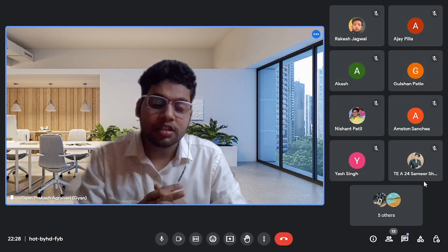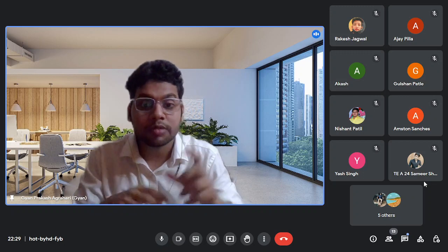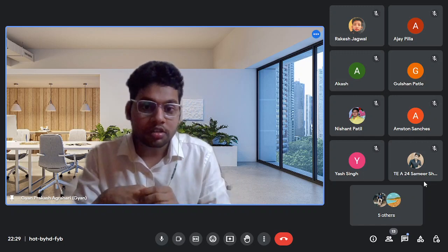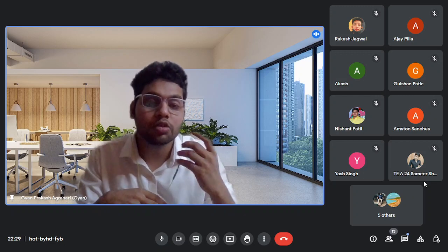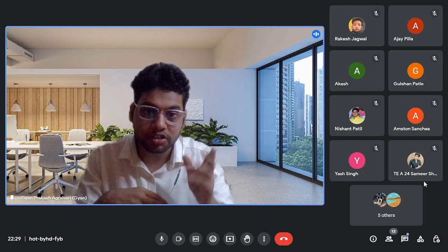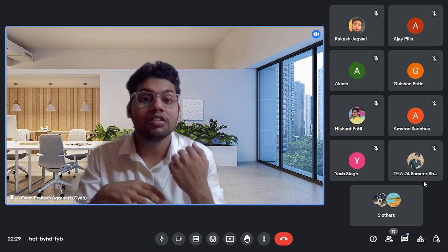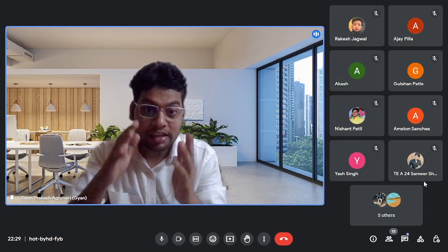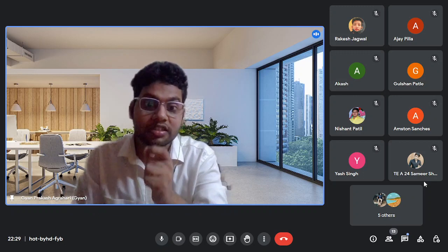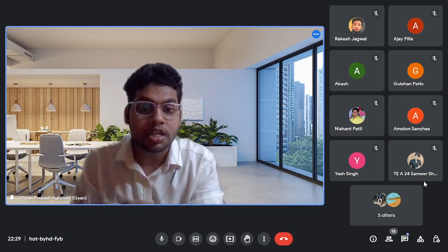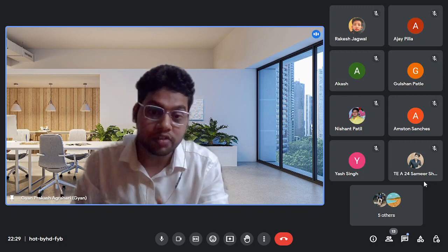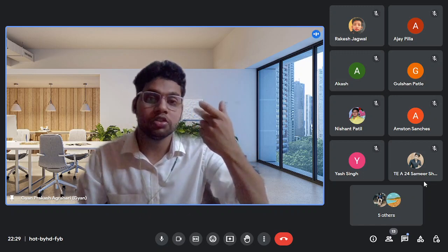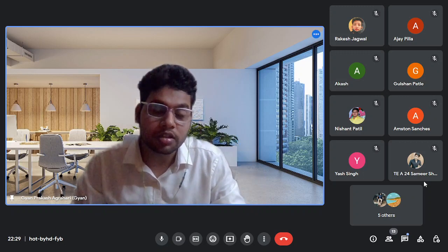So I said, firstly, the discharge pressure is created because of the design of the volute casing of the centrifugal pump, whose volume keeps on increasing. When we start the motor, the impeller rotates and imparts kinetic energy to the fluid particles because of the centrifugal force, due to which the fluid is displaced toward the discharge side of the volute casing. As the area keeps on increasing, the velocity will decrease, and hence kinetic energy will decrease according to the equation of continuity. And the moment kinetic energy decreases, it is converted into pressure energy. The pressure energy will increase. This is how pressure is created at the discharge side.